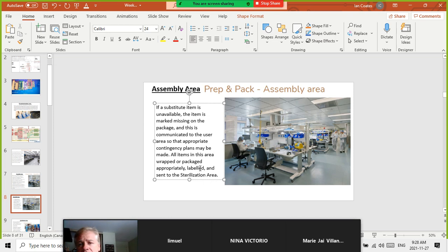So the decontamination area, that's where they receive things, take things down, break things down into their individual pieces. Then they send them on over to the assembly area where they inspect them. They repair if needed. You know, if you have a little rusty valve on an endoscope or something like that, it needs to be replaced. It needs to be put back together, reassembled. It's packaged, okay? So now it's ready to go to the sterilization area, okay?